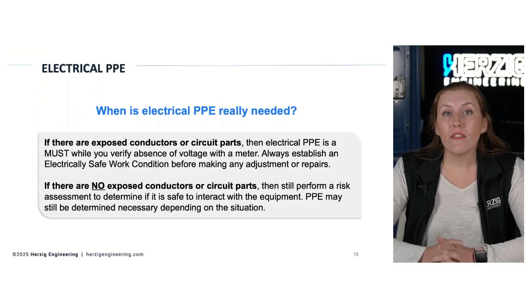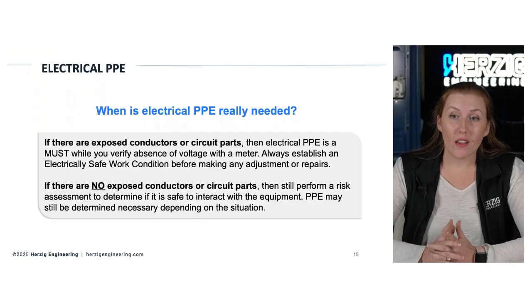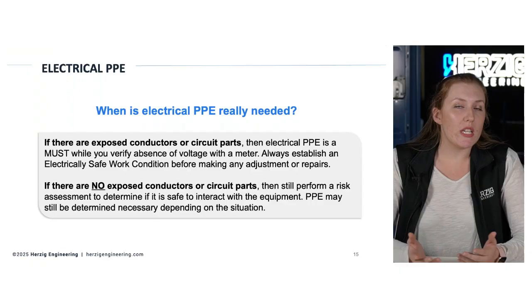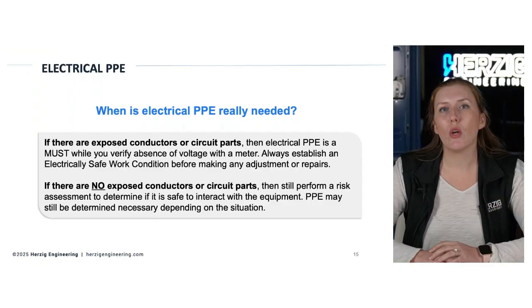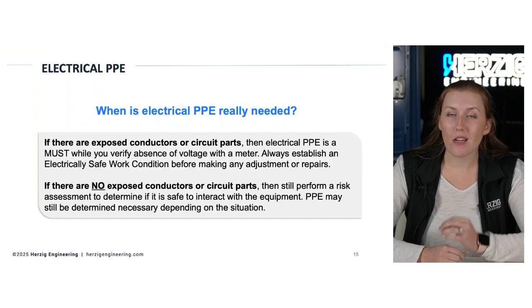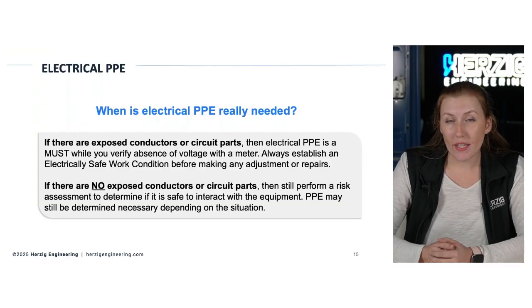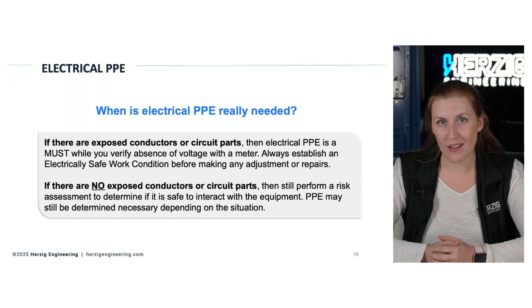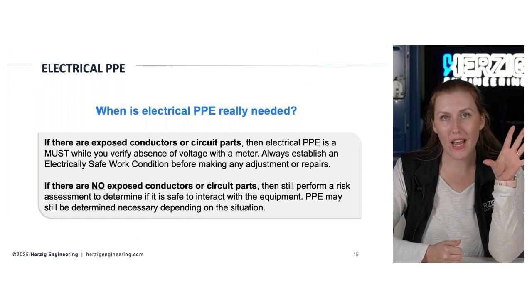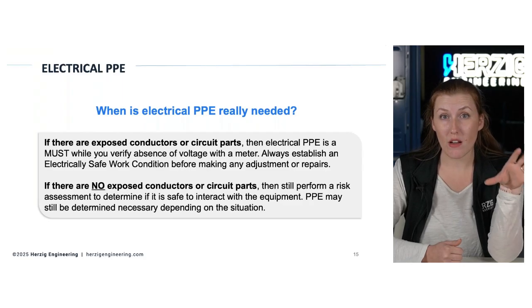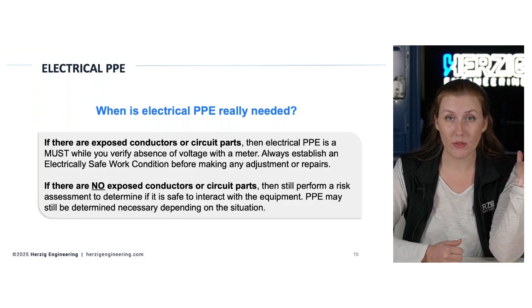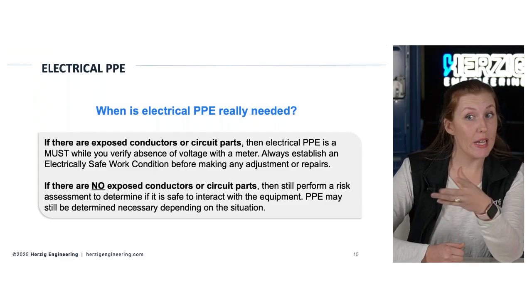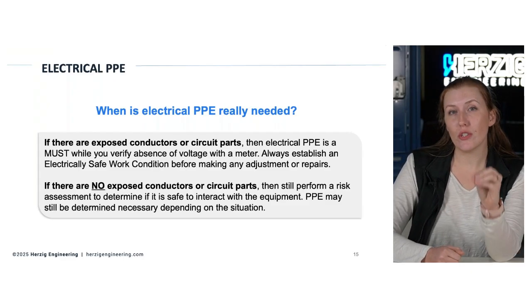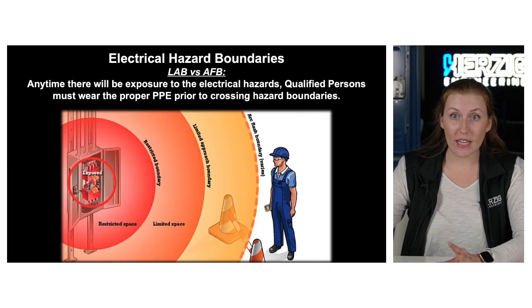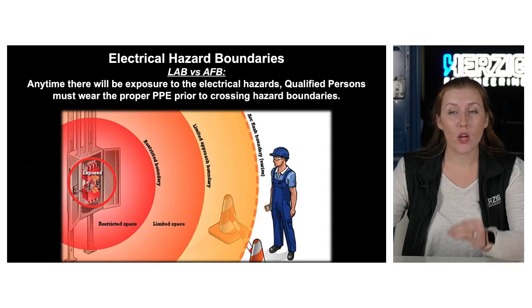If there are no exposed conductors or circuit parts, a lot of times people just totally disregard it - doors closed, covers on, no problem. Do your risk assessment. Sometimes what you're doing and why you're doing it could end up with exposure to those hazards, especially the arc flash hazard, because if it happens behind that cover and it's a strong enough event, it could blow covers off. We've seen it, we've seen videos, right? So PPE might still be necessary depending on what you're doing and why, but definitely anytime there's exposure and you're crossing the boundaries, qualified people need to wear the proper PPE.